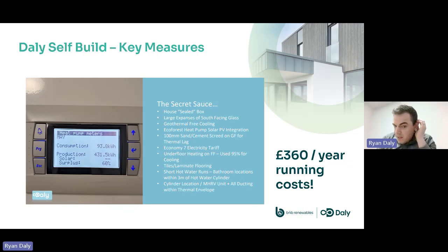We have a 100 mil sand cement screed on the ground floor. The idea of that is that you have a thermal lag. So when your heat pump is injecting a bit of heat at a low level throughout the day with the solar feeding it, the advantage is that your heat is coming up perfectly in the evening time when you want it the most. Whereas if you had a liquid screed, it's quite a bit more responsive, so you could feel that heat potentially a lot earlier in the day, which is what we didn't want.